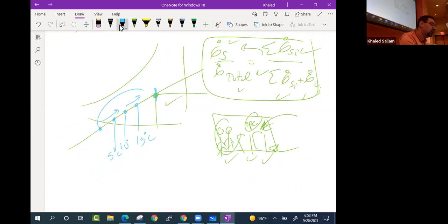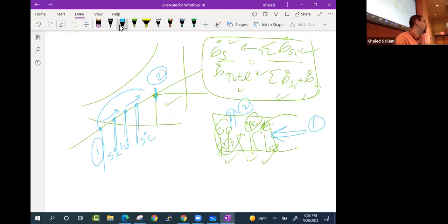Not the omega, no. So remember, we are sending 1 and we are pulling 2. This is 2 and we are saying where is 1. So what decides where should 1 be? I'm telling you, any one of those could be 1. It's the m dot air. So m dot air, H2 minus H1 is going to be the Q dot load.